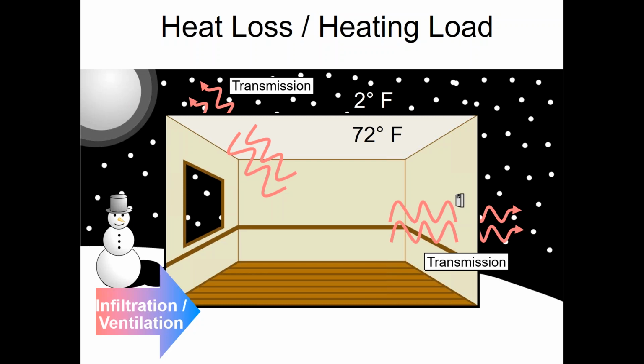Infiltration is also a factor, but if you guys were on the webinar on Monday, you'll know that I'm going to encourage you to really, really minimize that infiltration rate for anything that's been built certainly in the past 10 years residentially, and probably even longer than that for a lot of houses. That's all we look at on the heating side. We don't look at the solar gain on the heating side, because the worst case scenario for heating is that it's dark out and nobody's home. So people don't matter, lights don't matter, sun doesn't matter. Those things are all irrelevant for a heating load calc.